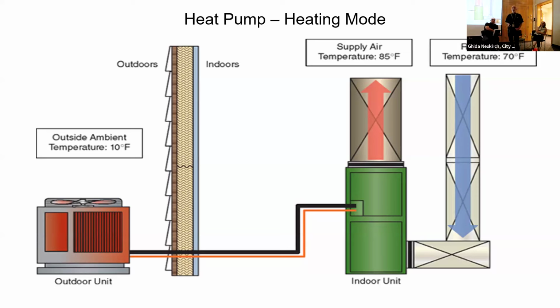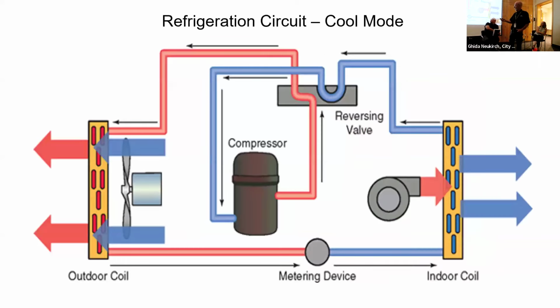Now, heat pump technology is changing a lot. If I go back to this guy, which is the heart of it so to speak, the mechanical side, the compressor, they're becoming way more intelligent. They can operate from 10% of their capacity up to 100%, and anywhere in between. That gives us the ability to run this heat pump in a wide range of ambient conditions. That technology has actually been around for about 20 years, believe it or not.